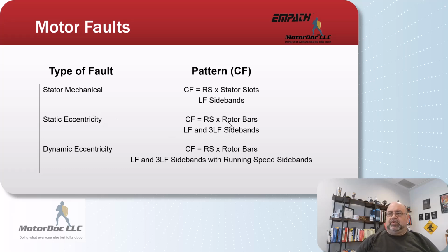Static eccentricity, as we talked about before. Running speed times rotor bars. Line frequency 3 times, often 5 times. Now, depending on the type of filtering you're using and everything else, just like vibration, but with this, sometimes the sidebands will be higher or lower. Sometimes they'll disappear. I've seen a lot of other bull and hype out there because, again, certain people don't understand what they're talking about. It depends on the filter or windowing you're using. You're going to end up with different size peaks.